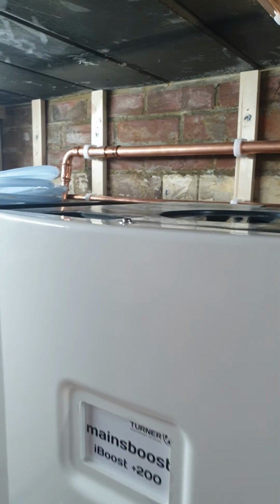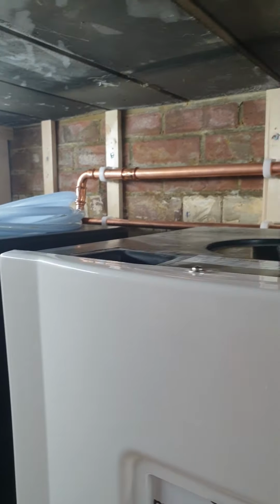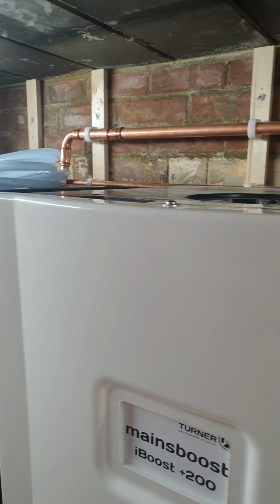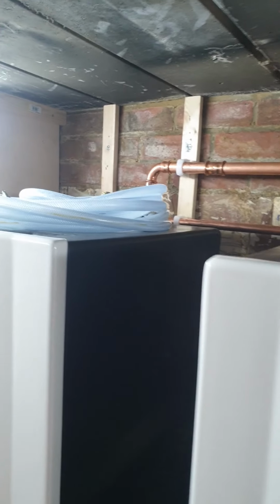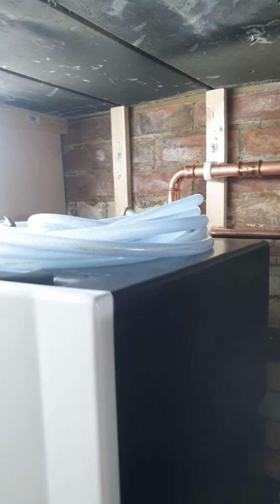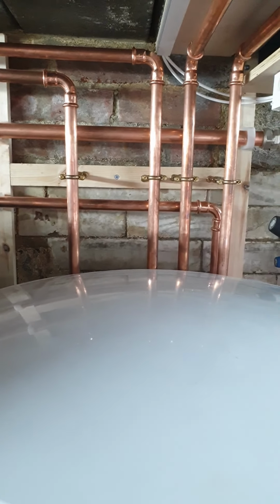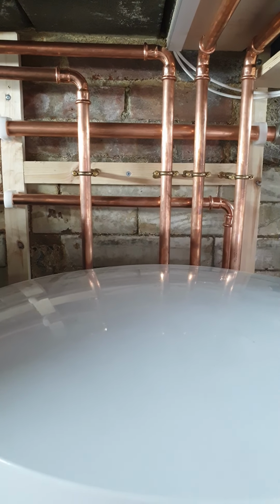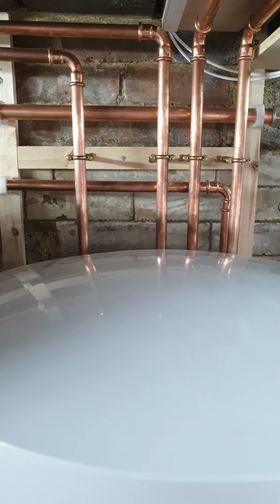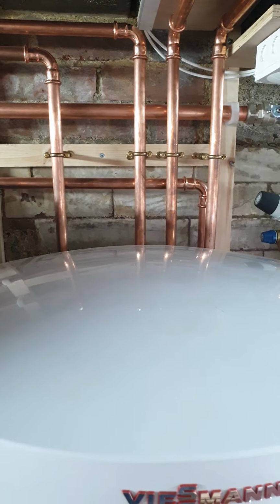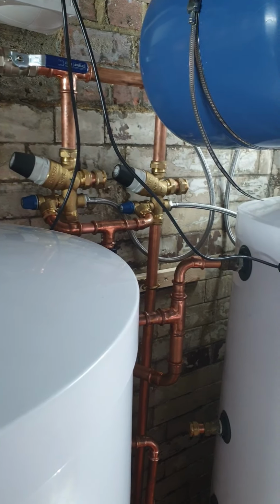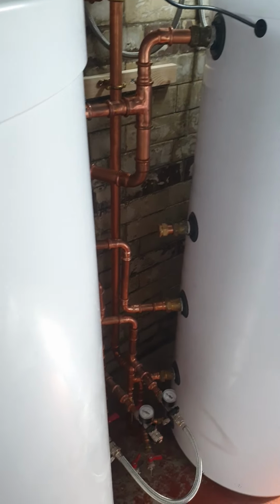This battening system was something I saw another guy do on a job and I thought was quite good. We didn't buy enough ply to ply line the whole place. I think that would have been a better job if we'd ply lined everything. But we had this batten idea and we've copied that, so we just run battens down the wall. These pick up any clips on your horizontal runs, and at any point you're going down, you put these cross battens in, which actually you can mount on top of the other battens. They don't need to be set back in the wall like that. They can actually run across the surface, and just mount your Munson rings on those. So, okay.